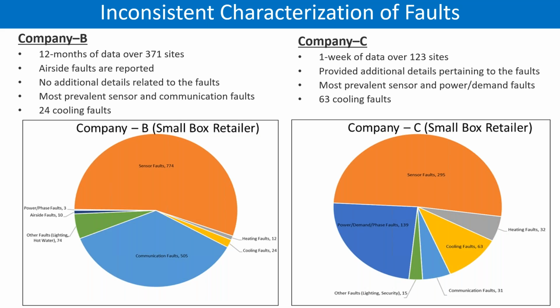The next sets of data we analyzed were for Company B and C. Both of these companies provided AFDD services, or systems rather, to the same small box retailer. There were differences in the raw data sets, and when we analyzed the data, we found consistency that they were both reporting around 50% sensor faults, unlike Company A, which reported almost 0 sensor faults. Second to sensor faults for Company B were communication faults, and second to sensor faults for Company C were power demand and phase faults. It was curious that there were so many sensor faults when analyzing Company B's data, but Company C provided a little bit of insight with additional details in their raw data set that allowed us to understand why this fault category was binned so frequently.